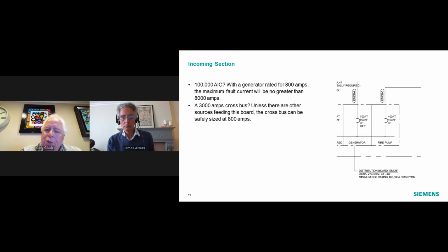The engineer also shows 3,000 amp cross bus. There's really no reason. We have one source coming into this switchboard. There's no reason that we need to oversize the bus. Let's just stick with 800 amps for that purpose.